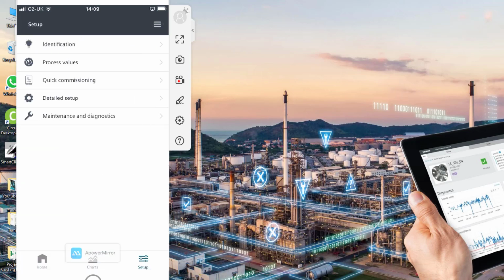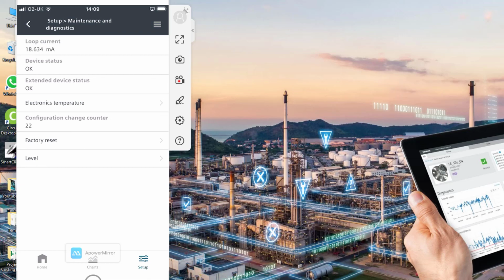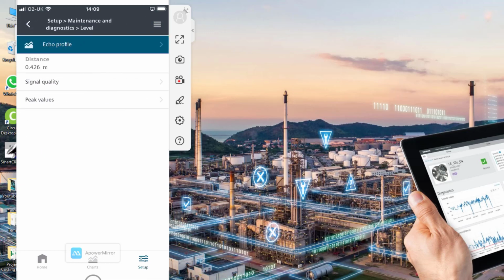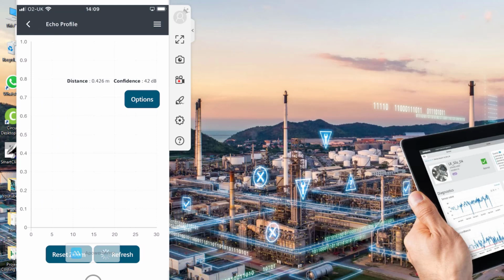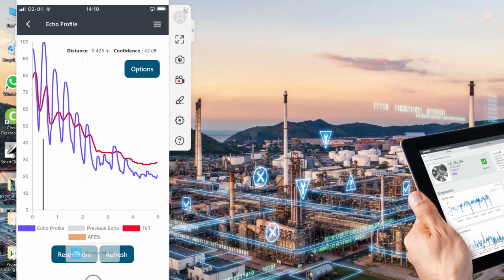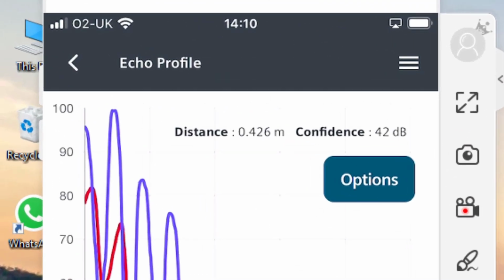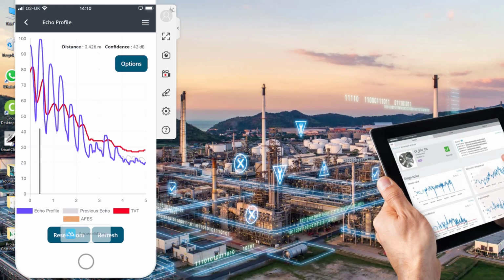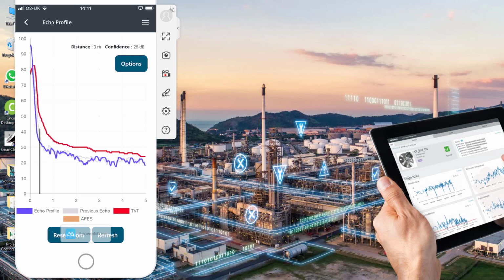And if we go to maintenance and diagnostics and then level, we can start having a look at some of the echo profiles. So that's set on my demo stand, which is about 400 mil high, and I'm going to lower this down so it's almost touching the floor. You can see there that there's no return echo even when I'm up nice and close, but it has latched on to the leading edge pulse, which is the first transmit.